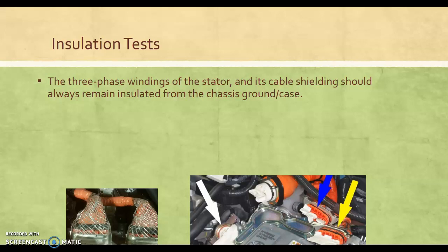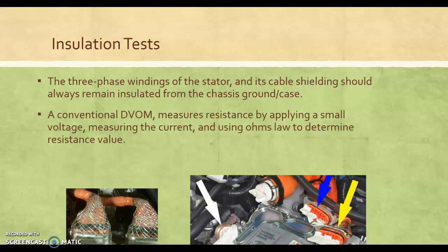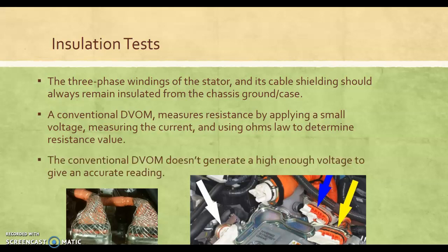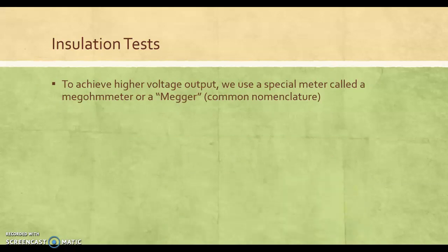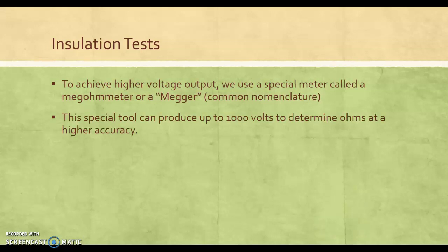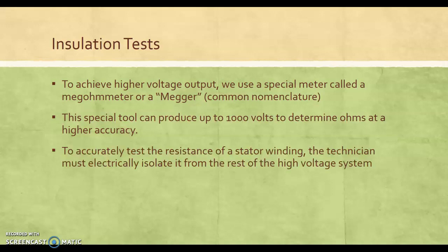But your testing procedure is identical to what you learned in 41. You're going to isolate the circuit, hook up the megohmmeter just like you'd hook up an ohm meter, and check for continuity to ground. The difference is you're going to push a test button, and that's going to send up to 500 volts through the circuit to do an adequate resistance check. So just something to think about. A tool that's needed is known as a mega ohm meter, insulation, isolation. I've heard all of these things. It's up to you what you want to call it.